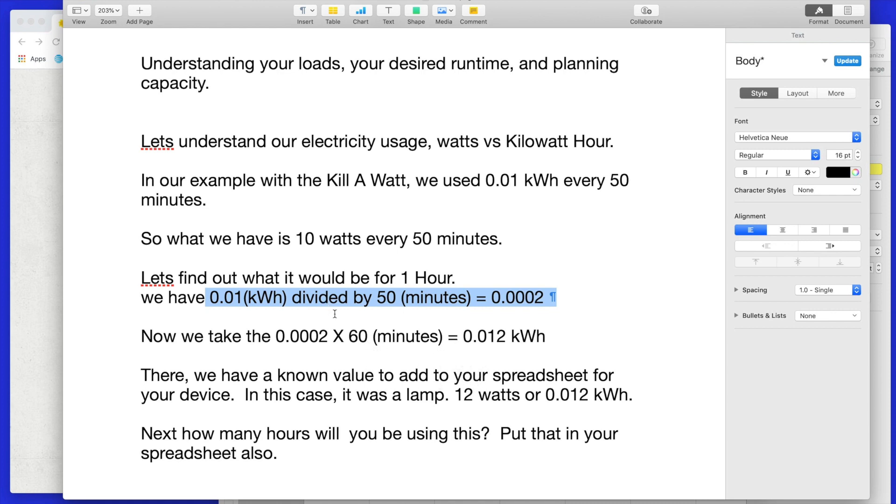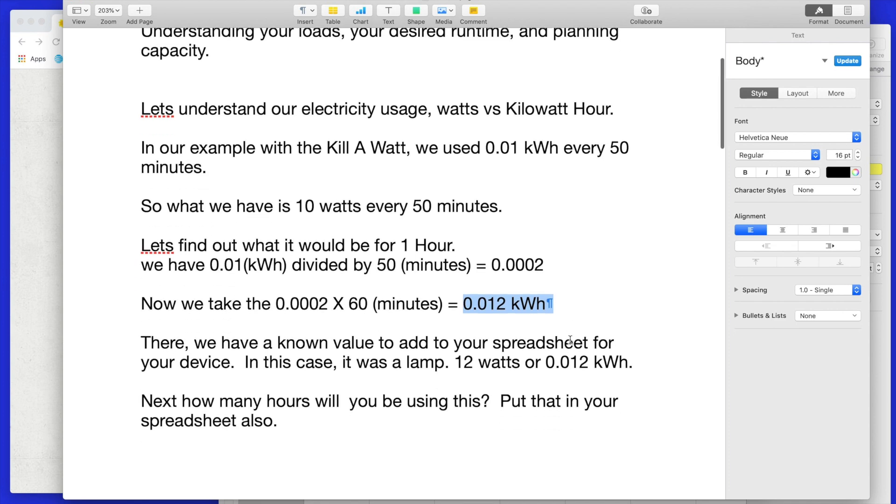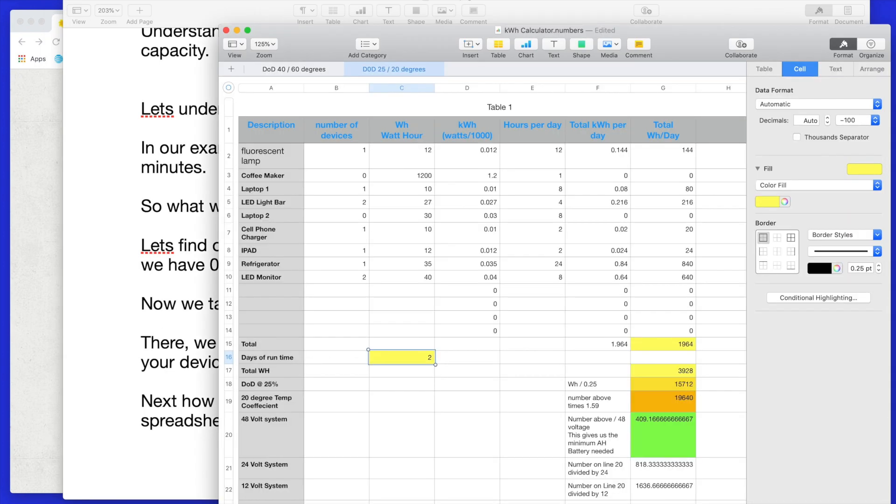So let's get back to it. We got our rate off the kilowatt meter. We divide that by 50 minutes. This gives us our per minute number. We take that per minute number, we times it by 60 minutes. Now we have a true hour, kilowatt hour value. So then we can add this to our spreadsheet, right? We know what it is.